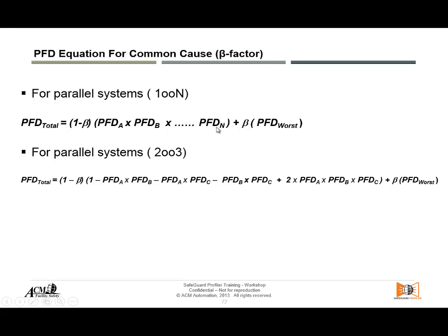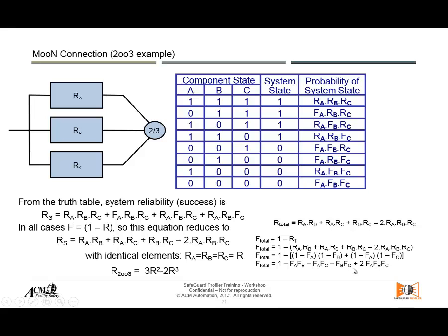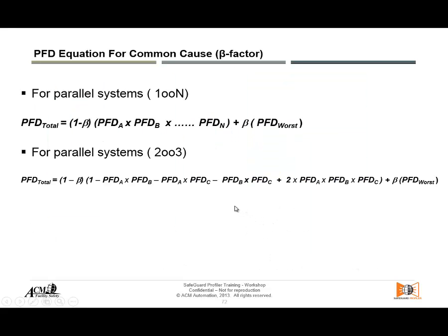When you have different technologies — for example a switch and a transmitter — each has its own PFD. You pick the worst one for the common cause term: (1 − β) × PFD_switch × PFD_transmitter + β × PFD_switch. This is the formula for a parallel system including the beta factor. Using these rules of reliability block diagrams, we can calculate any architecture simply by knowing each component's individual PFD.